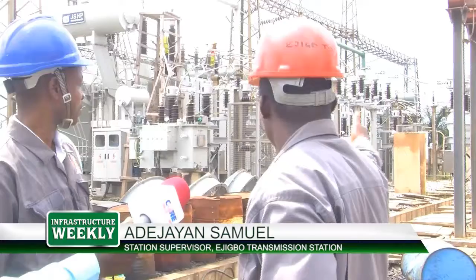They've changed so many pieces of equipment, like this circuit breaker. Something that will withstand 100 MVA will be of higher rating than one that withstands 30 MVA. This one here is a secondary circuit breaker, and likewise the primary circuit breaker has been changed. Also the isolators — from this side downward is the incomer, and this is the outgoing. They've changed everything, like our GT giving us station supply, and they've replaced that too. So all these, the CTs, isolators, and breakers, up to this level, have all been changed in order to conform with the present capacity.